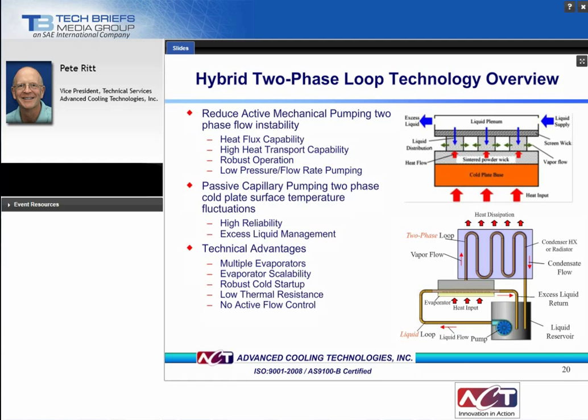At the evaporator, the passive capillary-driven two-phase loop acquires and delivers large, high heat flux loads through vaporization and condensation. The benefits of this approach are many. With a steady supply of liquid, high heat fluxes can be dissipated efficiently. No portion of the system is highly taxed, ensuring robust operation with minimal pumping requirements. A key feature is that the system can accommodate multiple evaporators, each of which can have unique power dissipation requirements.